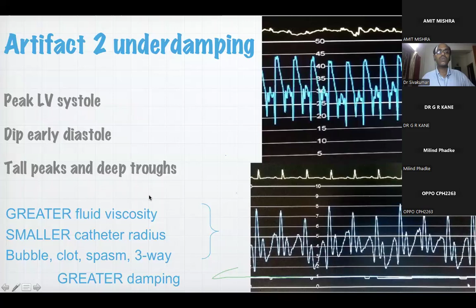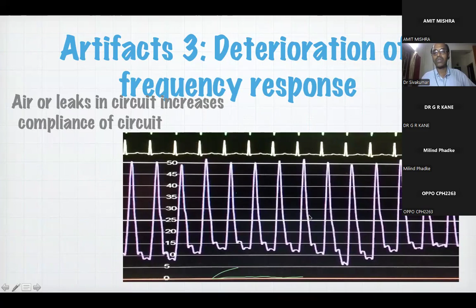The third one is deterioration of frequency response. This is a pulmonary artery pressure curve. If you look at it, the waveforms are totally lost and it is having multiple steps. This is basically the frequency response getting worse and worse. If you can fill the fluid, aspirate the entire fluid and replace it with saline, sometimes it may get better. If it is not getting better, you have to change the transducer.